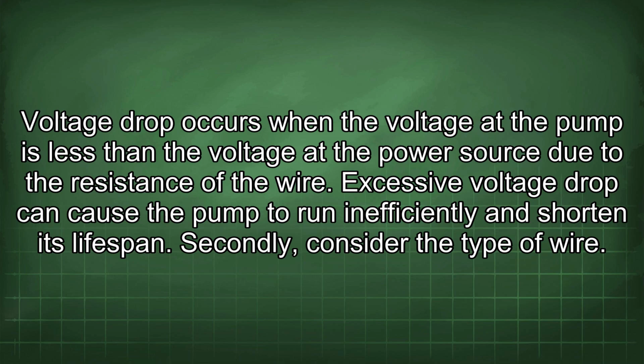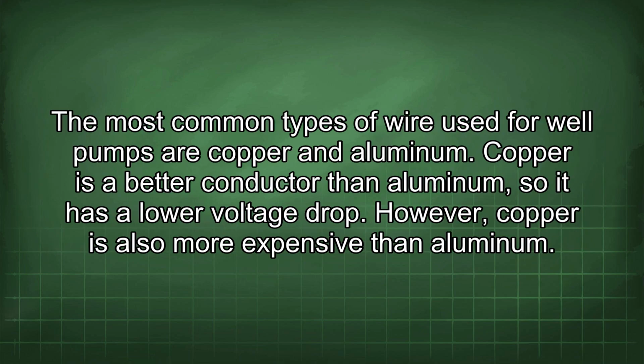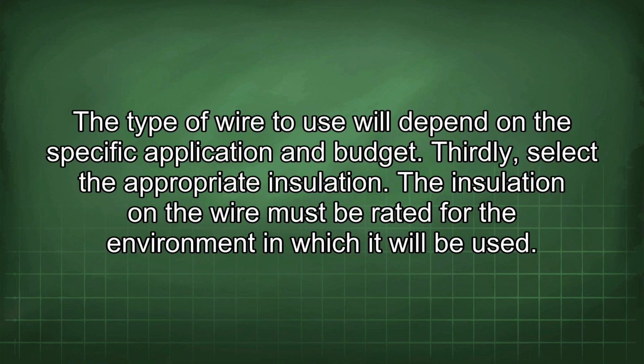Secondly, consider the type of wire. The most common types of wire used for well pumps are copper and aluminum. Copper is a better conductor than aluminum, so it has a lower voltage drop. However, copper is also more expensive than aluminum. The type of wire to use will depend on the specific application and budget.